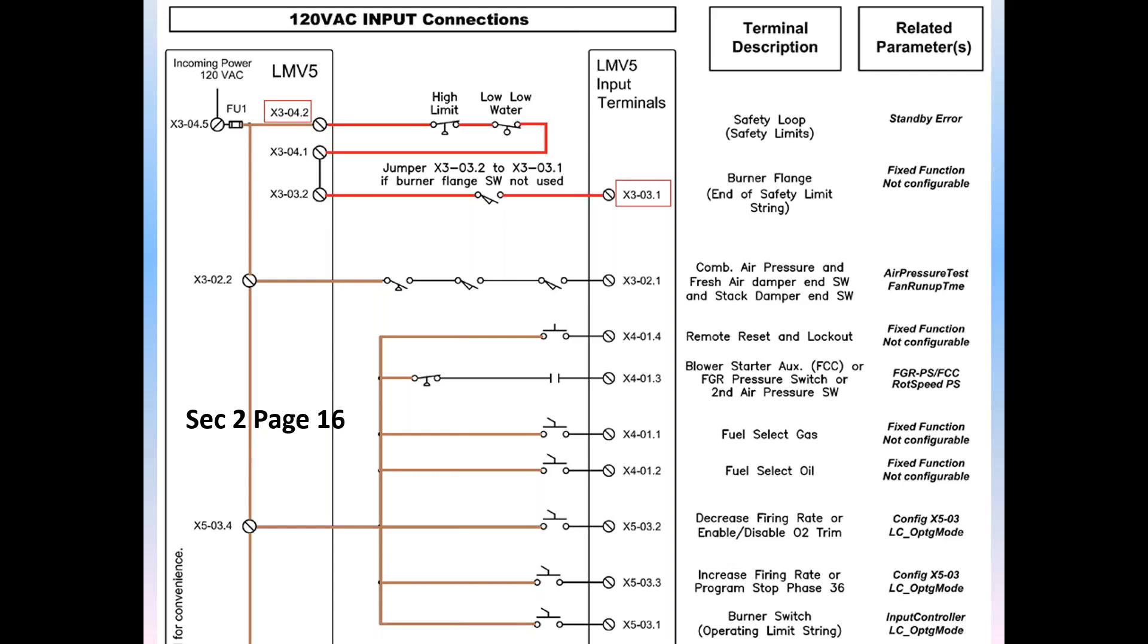In this slide I also like to point out the safety loop, shown above in red. It starts with X304.2 and finishes with X303.1. Items in this circuit are lockout non-recycled devices, such as high pressure, low low water, and in many cases of the European burners, a flange switch to prove that the burner is in fact engaged with the boiler.